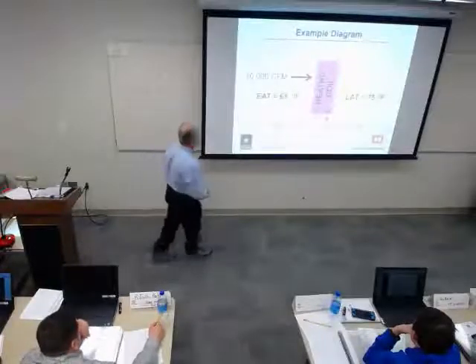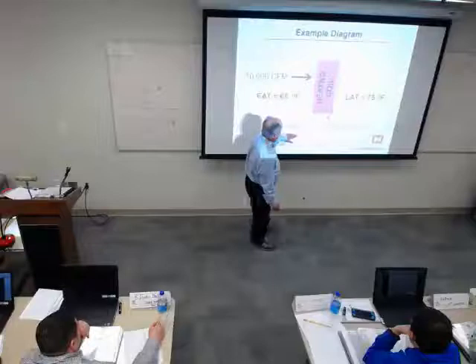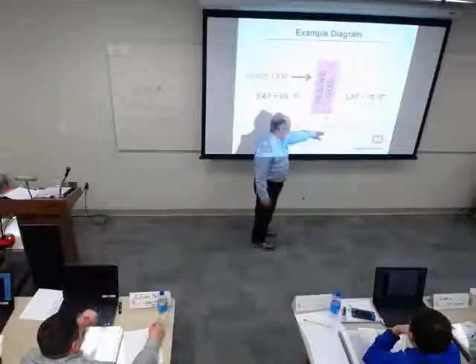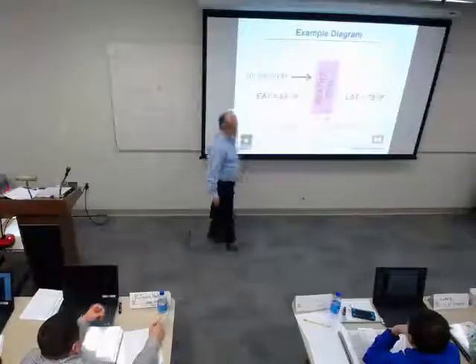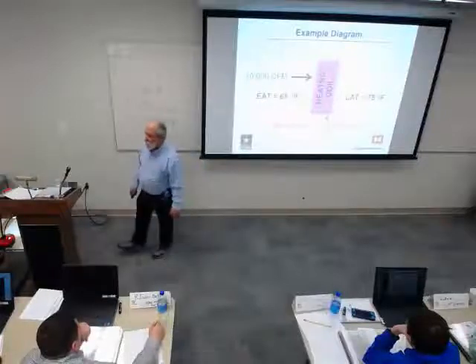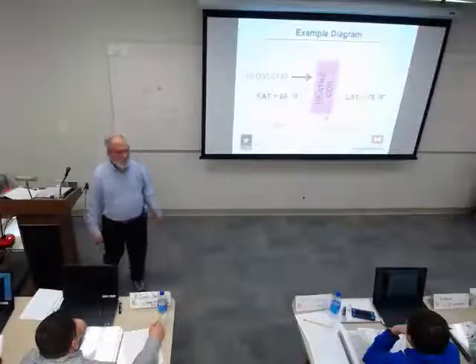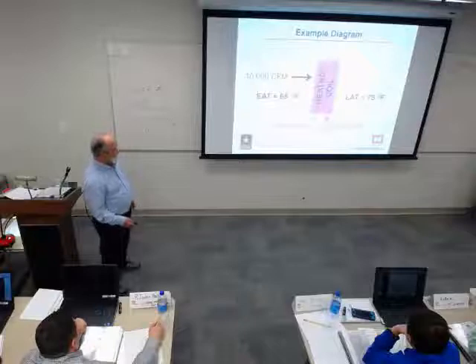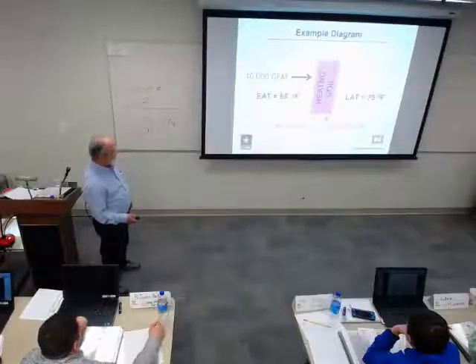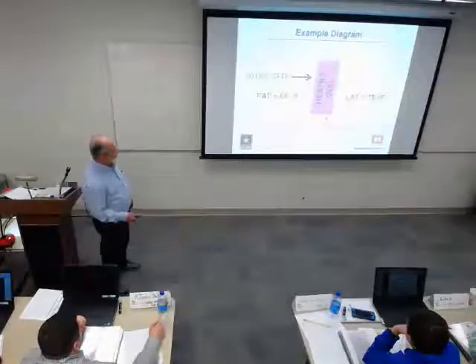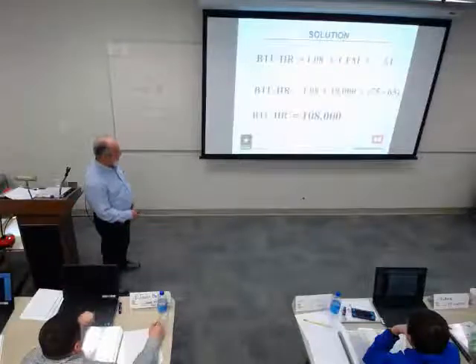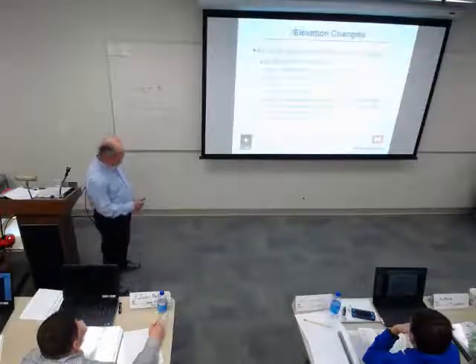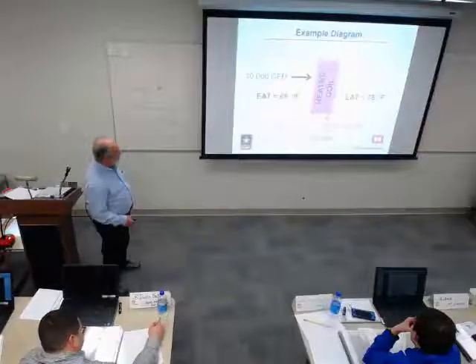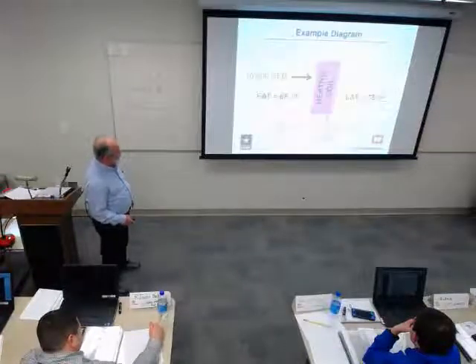And then if we look down here at the water side, water's coming in at 180, entering water temperature, leaving at 160. Those used to be temperatures we saw a lot. We're seeing a lot less of them now, but that's the concept. So water is being cooled, air is being heated. Okay, that's all right. So let's look at what we're doing here.